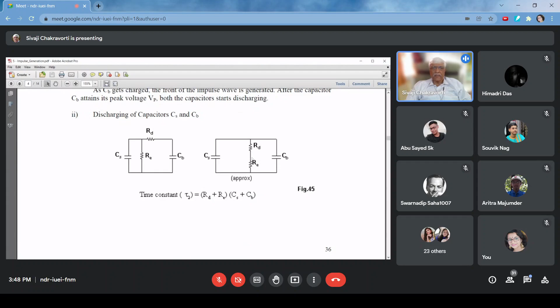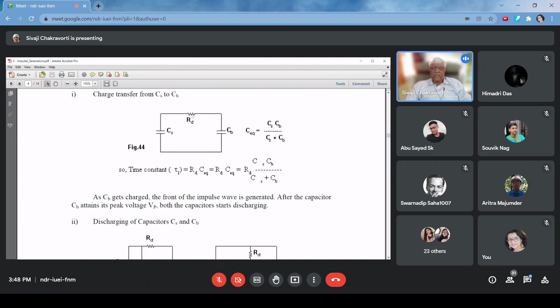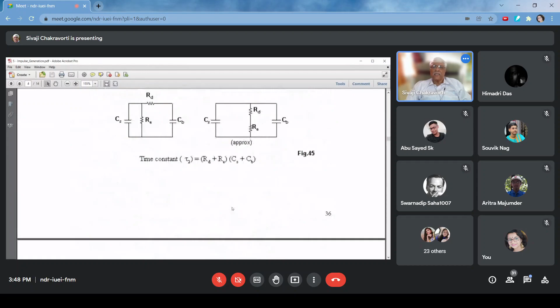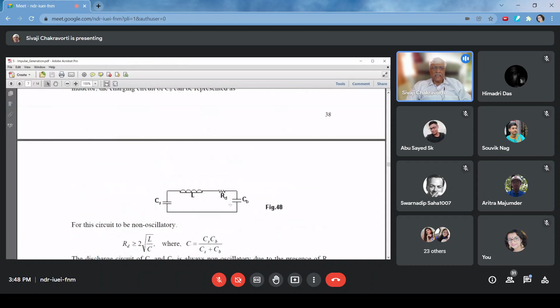The entire problem comes only during charging, that is figure 44, where only RD is in series. If RD does not have the required value, you will get superimposed oscillations on the front time instead of a smooth waveform, and that is not permissible as per the standard. That is the significance of RD, and that is why it is called the damping resistor.